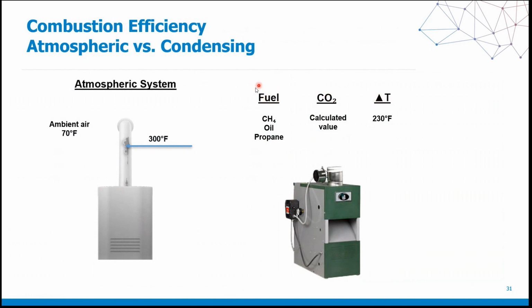So when we turn on our analyzer outside in fresh air, which I just went over, one of the things we want to make sure is that we're set up on the proper fuel type. Because if we're not, that's going to impact everything else that is going to follow suit. And why I say that is that when you select the proper fuel type, your CO2 readings are going to come up and be calculated correctly, because CO2 is a calculated value. It is calculated based on the oxygen percentage.